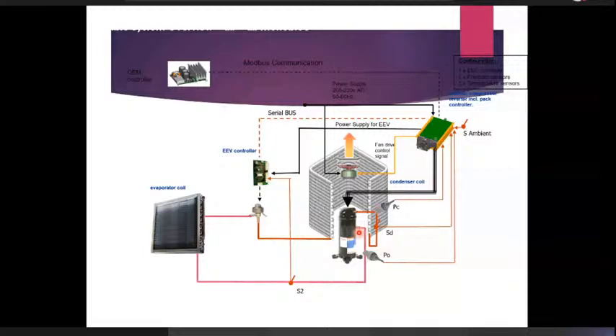Then do we need to run the condenser fan at its full speed all the time, or do we need to vary the speed? What is the ambient air temperature? The ambient air temperature can help us determine whether we need to run it at full speed or part of the speed. And the pressure that we get from the condenser also tells us how well we are doing on the airflow characteristics, because we need to maintain a certain pressure for heat rejection. We need to maintain a certain pressure drop across the expansion valve for refrigerant flow to happen.